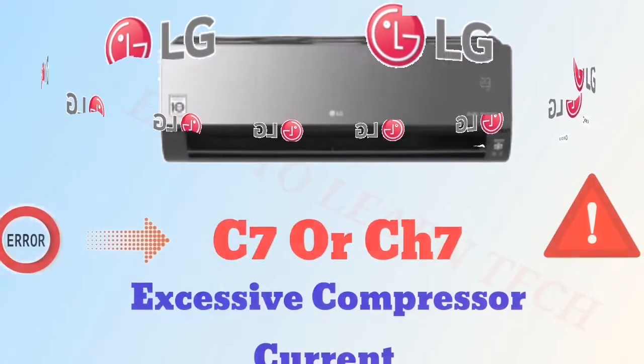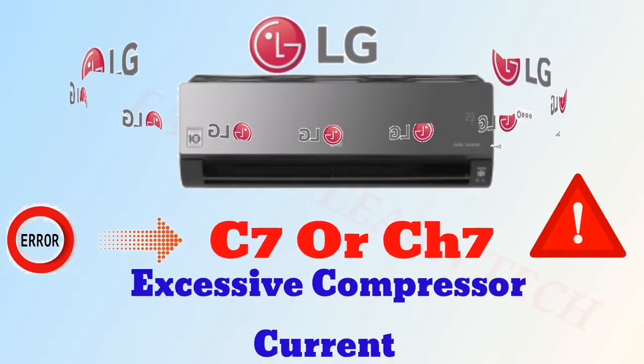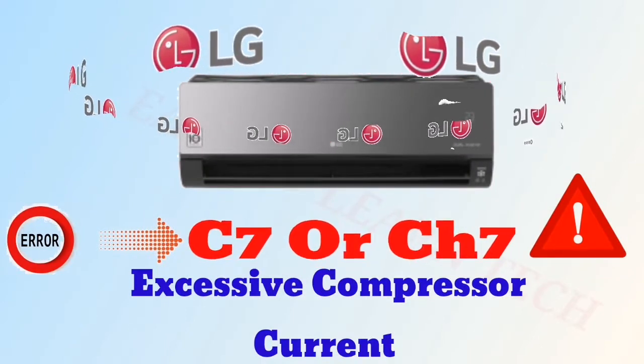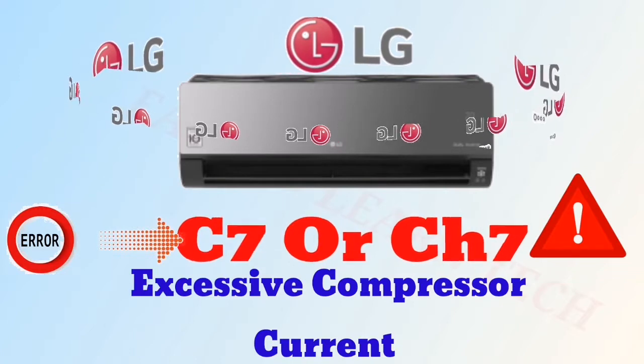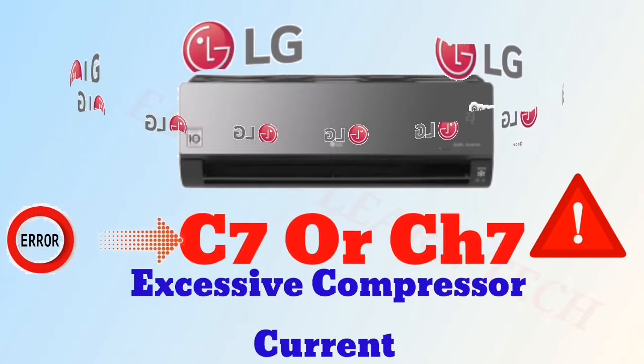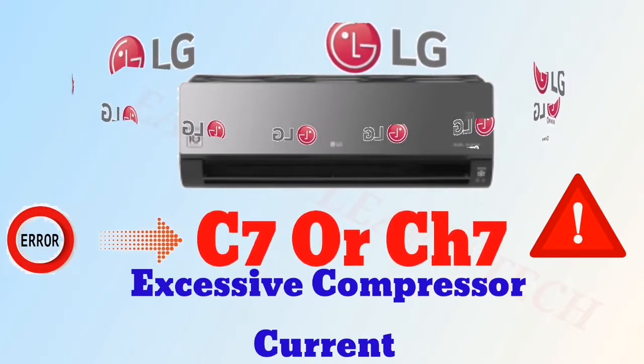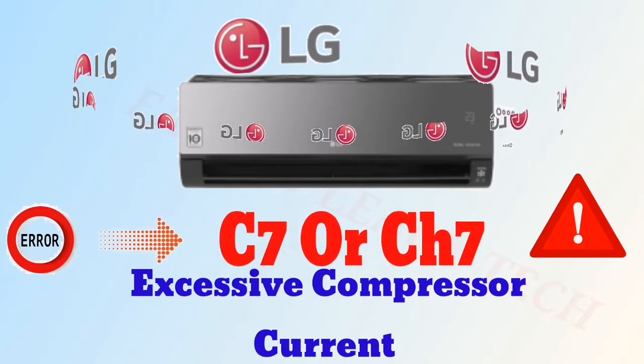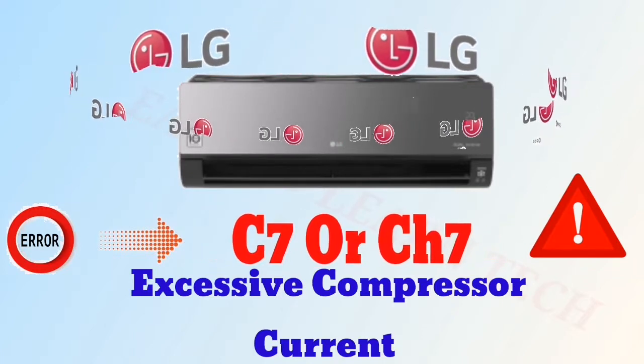When you see error C7 or Ch7, it means compressor overcurrent. First of all, you have to check whether the compressor is overheated or not. If your compressor is overheated, then you have to cool the compressor and start the unit again. And if it works, it means the problem was due to the overheating of our compressor.